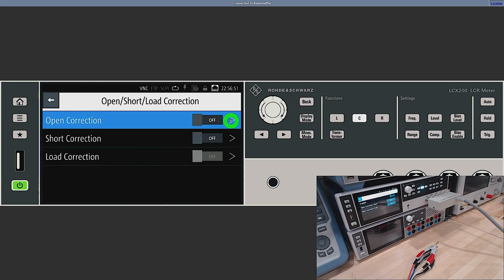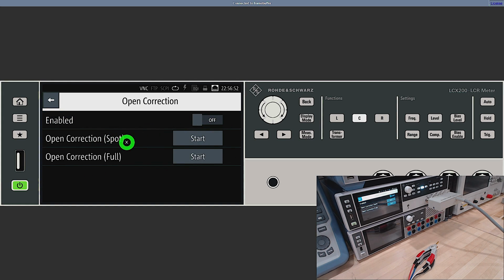Now under open correction we have two additional options. We can do it on the spot, meaning that the setting that the instrument currently has is what the open calibration will be applied to. Or you can do a full calibration where the instrument would sweep across its internal frequencies and settings to make sure that if you ever change something, you still have those calibrations in the memory. The full one obviously takes a lot longer.